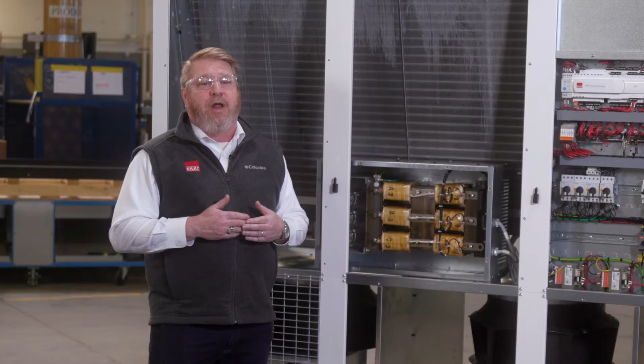So the most common way to vary the speed of a piece of mechanical equipment, whether it be a fan or a pump, is either to use an electronically commutated motor, which is probably the most common fan motor in the data center today, or possibly using a VFD for a fan or a pump. The difference is simply how these components go about varying the speed of the mechanical device.